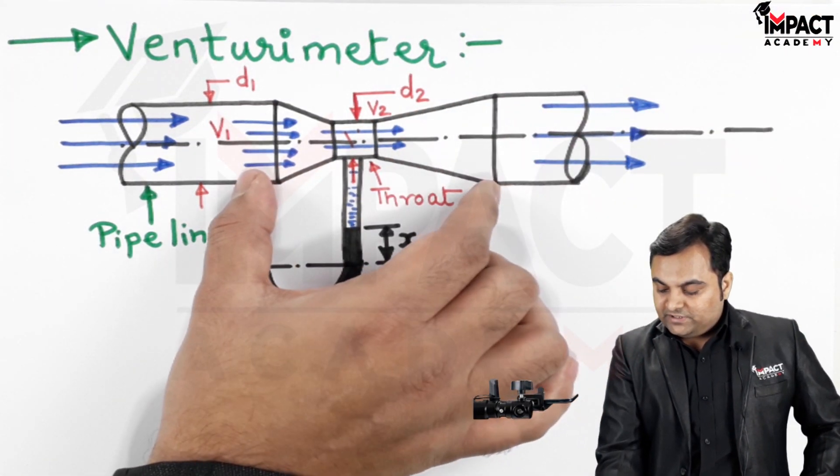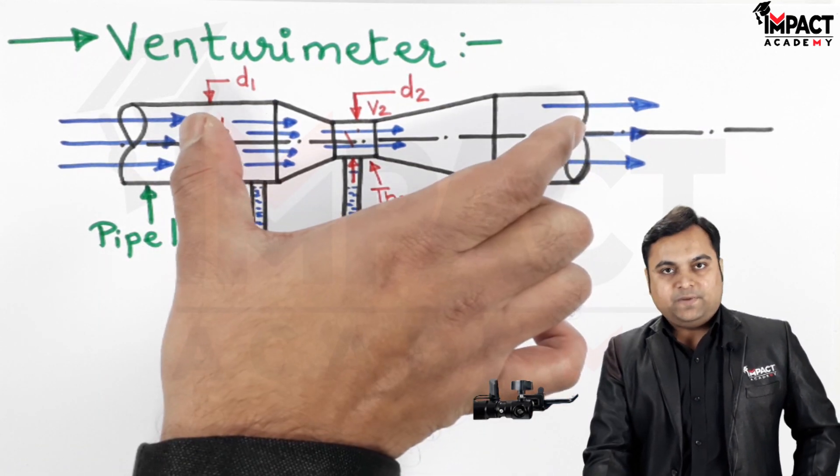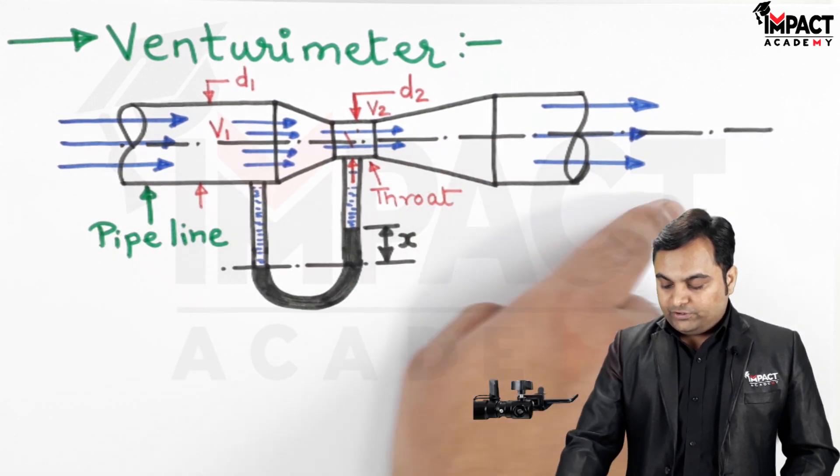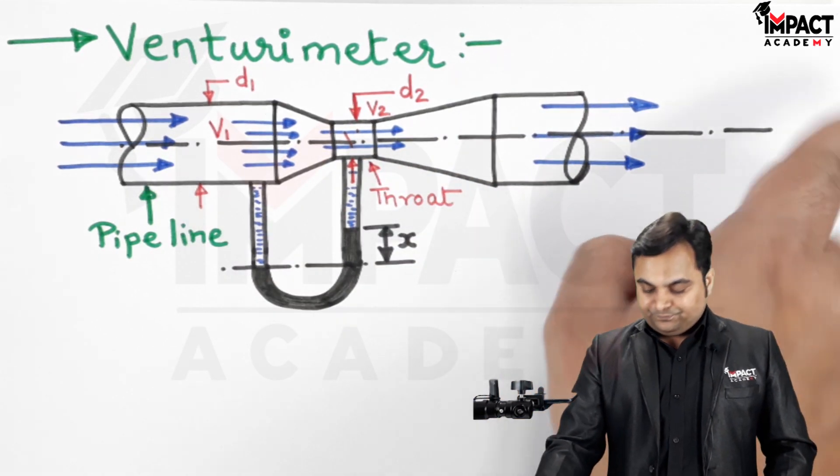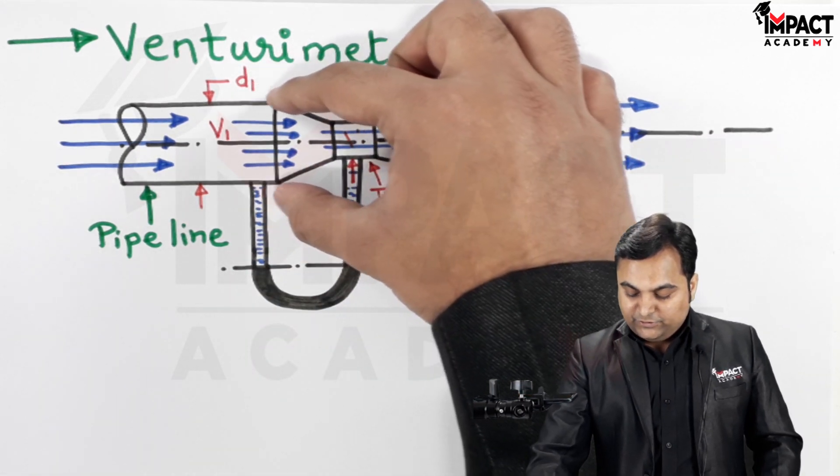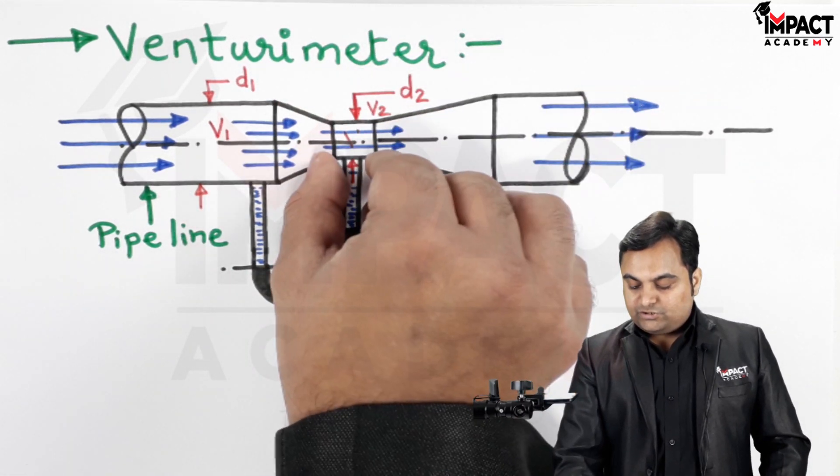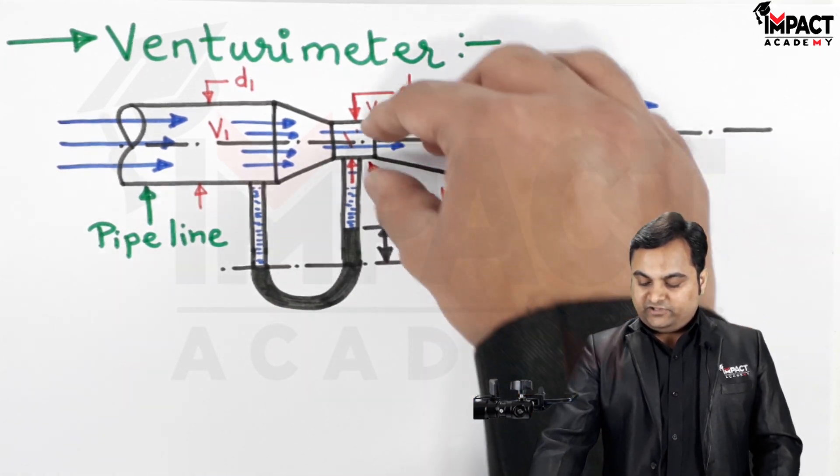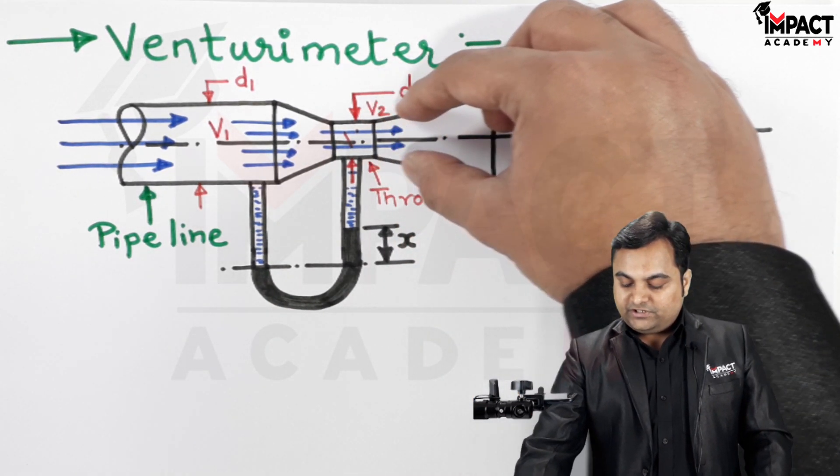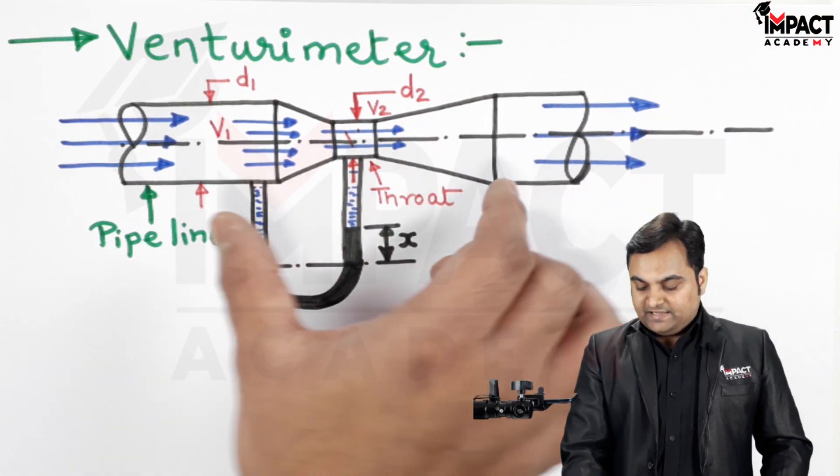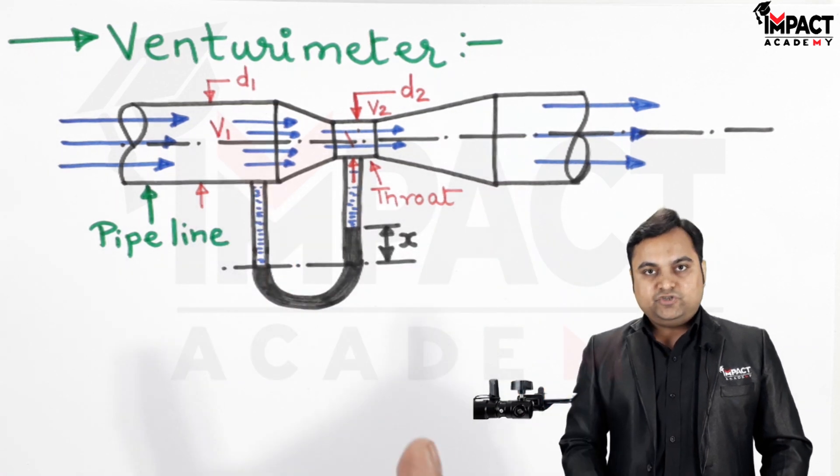Venturimeter is the device which is connected in between the pipeline when we want to measure the discharge or the flow rate of this flowing liquid. It has a convergent part where the diameter reduces first, then it remains constant for a small amount of length called as the throat section. After that the diameter goes on increasing again up to the pipe diameter, that is a diverging cone, and this complete device is called as the venturimeter.